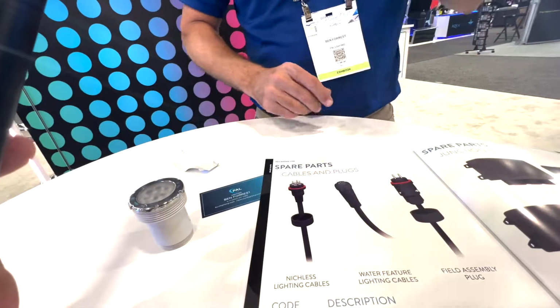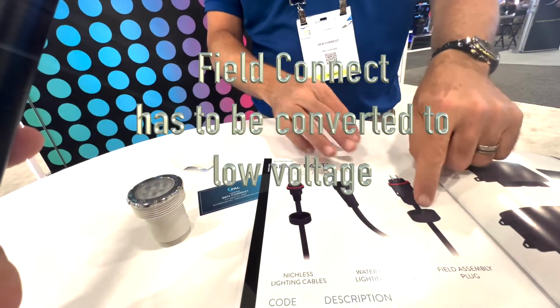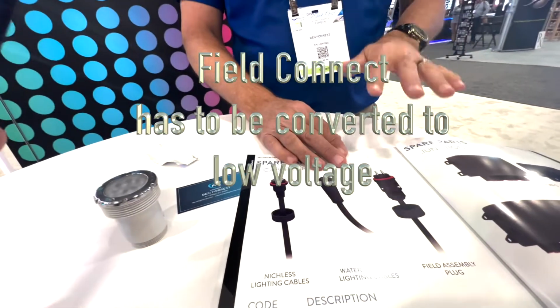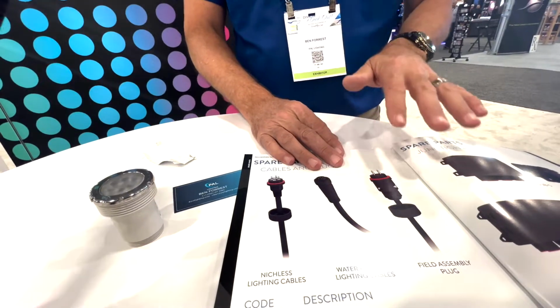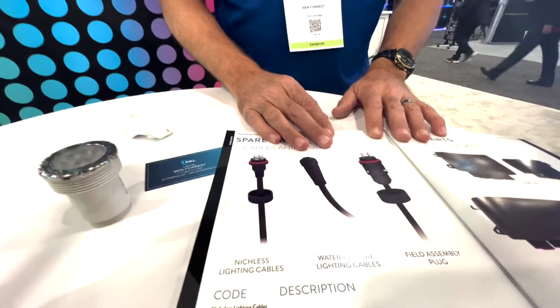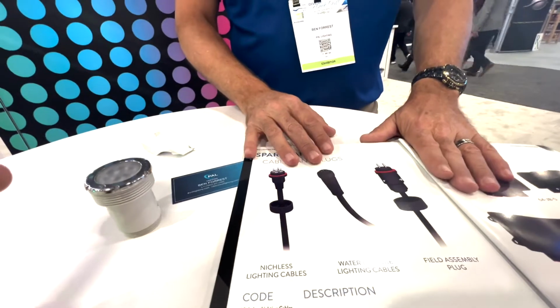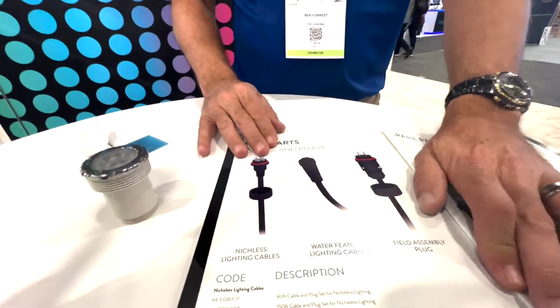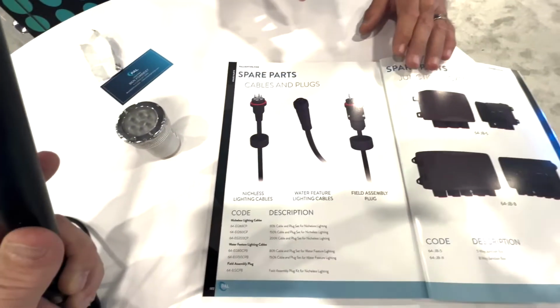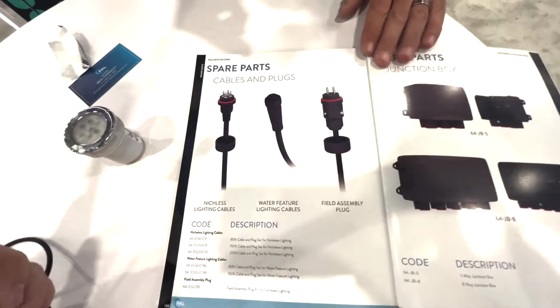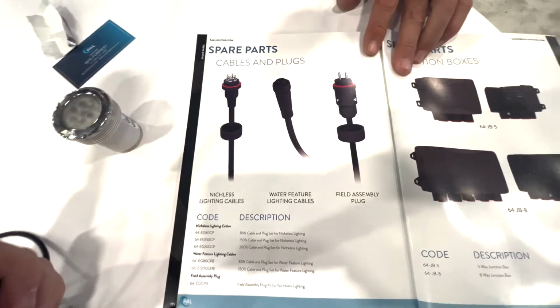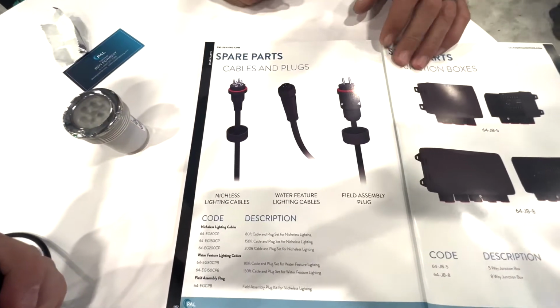They have to go low voltage. The Field Connect plug is only UL approved for low voltage, 12 volt AC or up to 40 volt DC. These are UL listed, UL approved. But if they're replacing a high voltage light, they've got to put a transformer on it so that the new light is only low voltage.